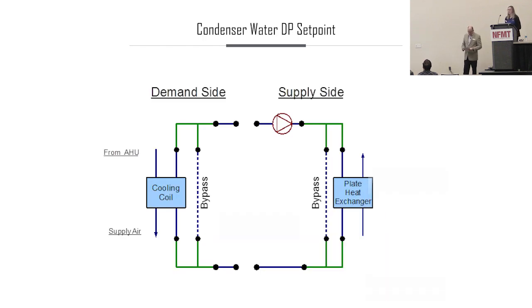So for this setup, we had a condenser water loop, and it was just running at a constant DP set point. So we were able to implement a reset for that DP to actually maintain a differential temperature of 10 degrees between the supply and the return through that loop. A lot of water systems endure through low delta T syndrome, where it's not really ever doing much cooling. And so if you want to maintain a certain delta T, then there's a direct relationship with the flow through the system for the capacity of that loop. And so if you reduce flow, then you can increase delta T and vice versa.